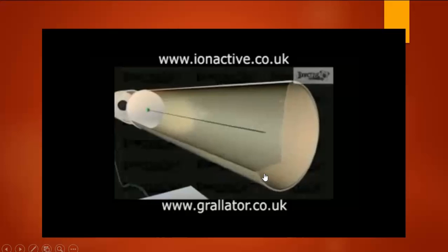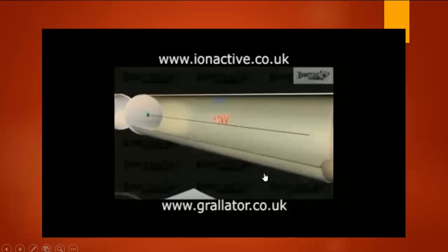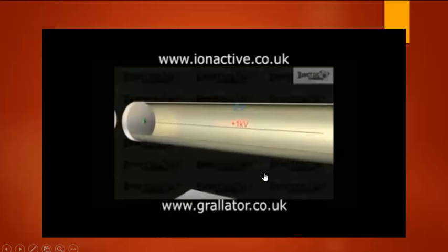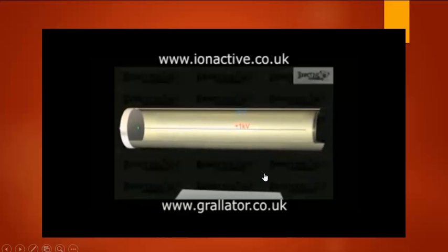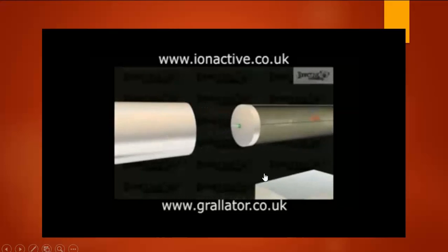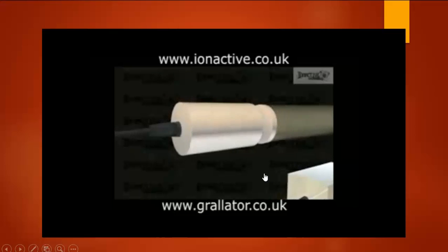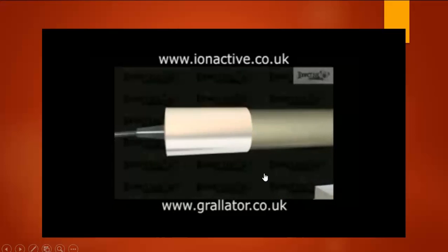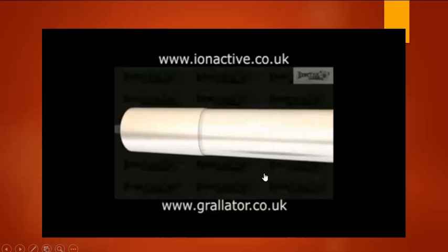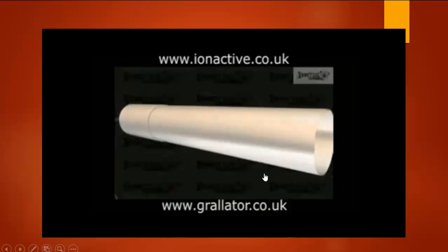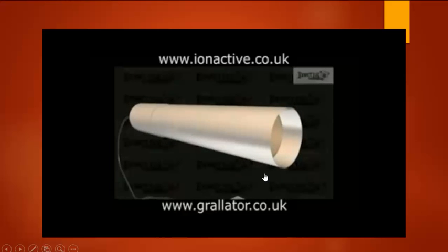The inner wire and the outer cylinder are maintained at a potential difference of about 1 kilovolt, and in the absence of radiation, no current can flow through the inert gas between the central anode and the outer cathode. The connections are made via wires into a connecting housing that fits over the rear of the tube. An outer tube guard will typically screw onto this to protect the actual GM tube. This tube guard can be open at the end or be covered by an end cap energy filter to change the energy and particle sensitivity of the device, or, if a carefully calibrated design is used, allow for ambient dose measurements rather than ambient count measurements to be made.